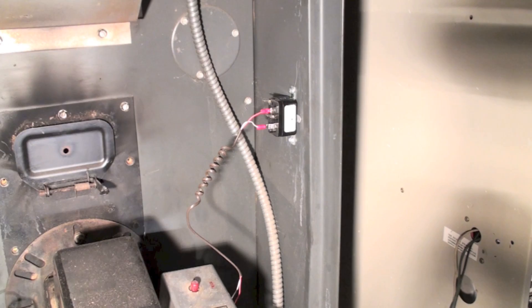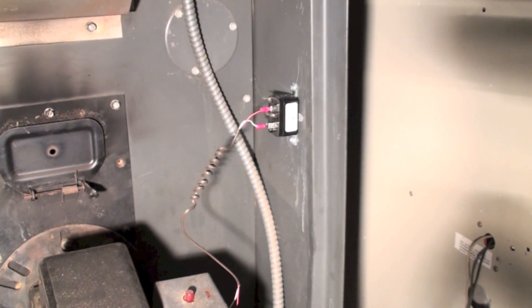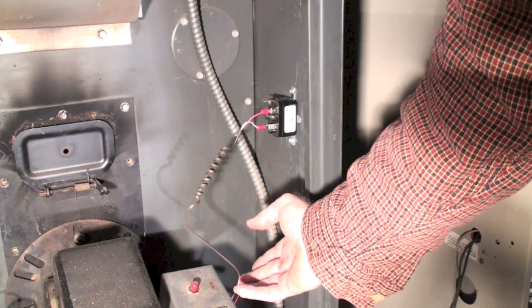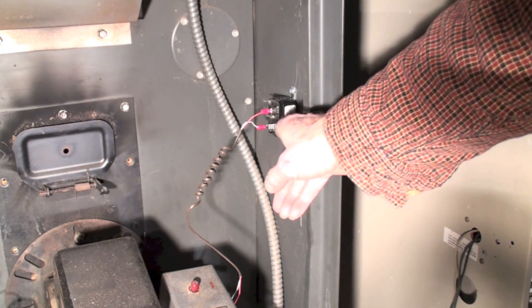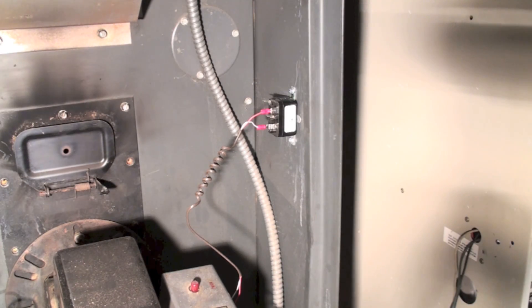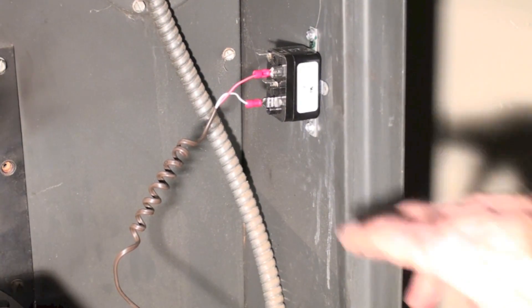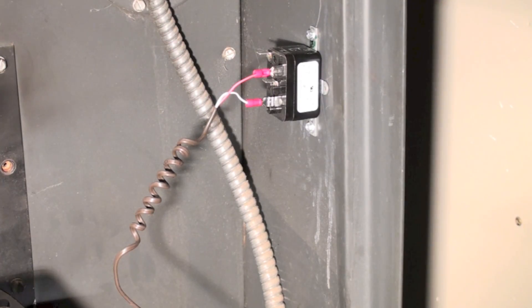Okay, the first operation is complete. What I've done is, if you look down here, these are the wires that came from the thermostat. I have wired them to number two to number four on the relay, so they're mounted on the normally open switch. When I energize this relay, it's going to turn on the oil furnace. Now it's completely isolated at this point.